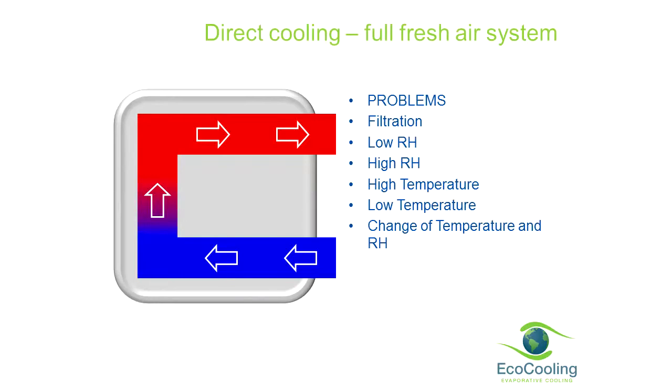So, why is it unacceptable? Just direct, in the simplistic form. We've got, common sense, we've got to filter particles out of the air. We can't necessarily accept widely varying rates of change of RH, low RH potential static electricity problems, high RH increased corrosion rates, etc. High temperatures, obviously a no-no.